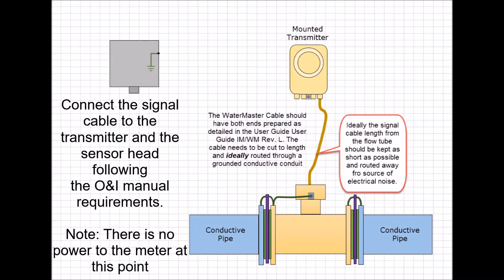The flow tube signal cable should be prepared as specified in the WaterMaster user manual. The cable should be routed through its own conductive conduit for optimal noise suppression with no other wiring or cables. The cable length should be kept as short as possible. Looping excess cable and splicing additional cable is prohibited. All wiring on the meter must be performed with power disconnected from the meter.